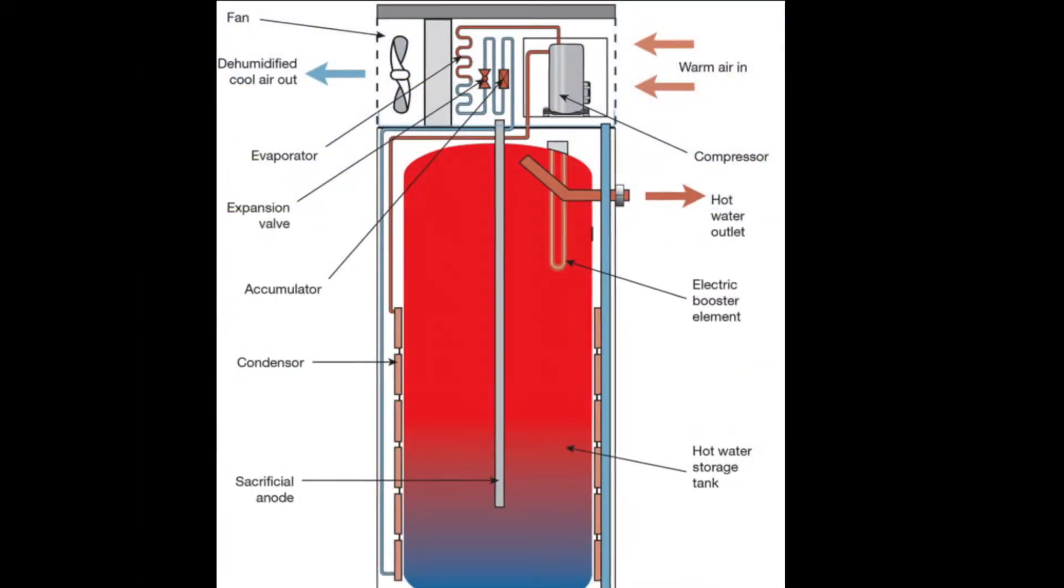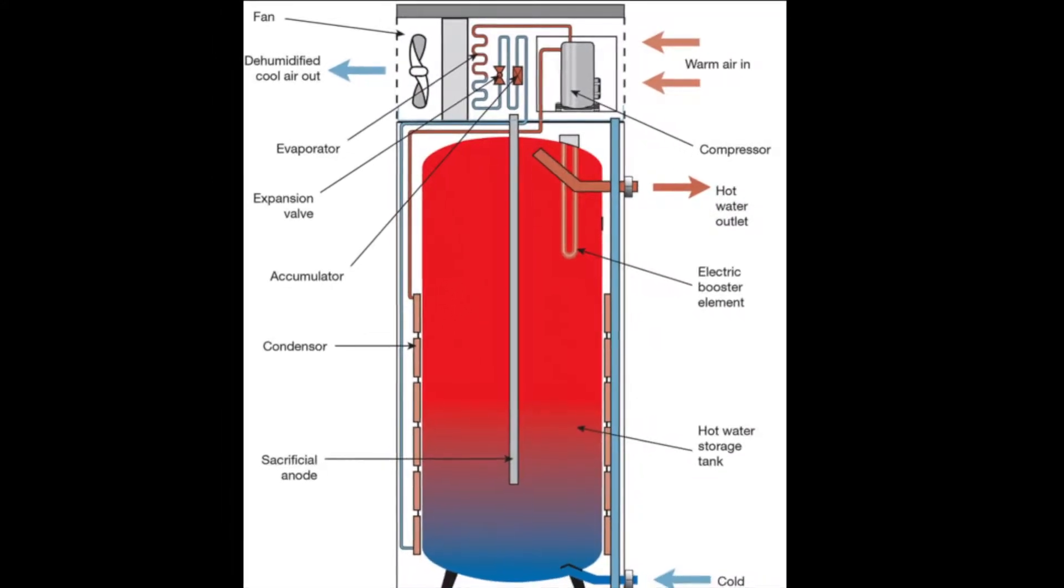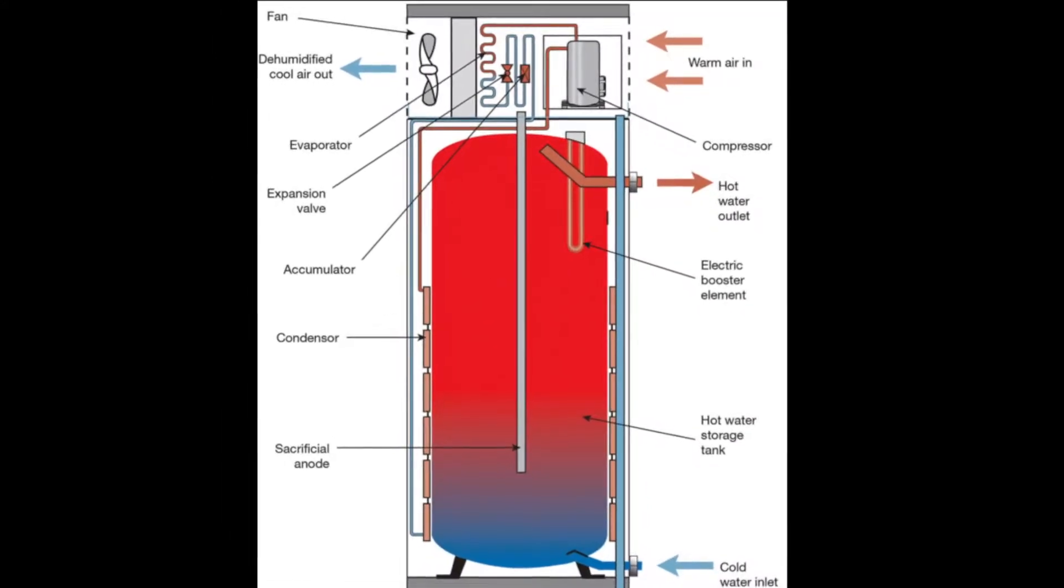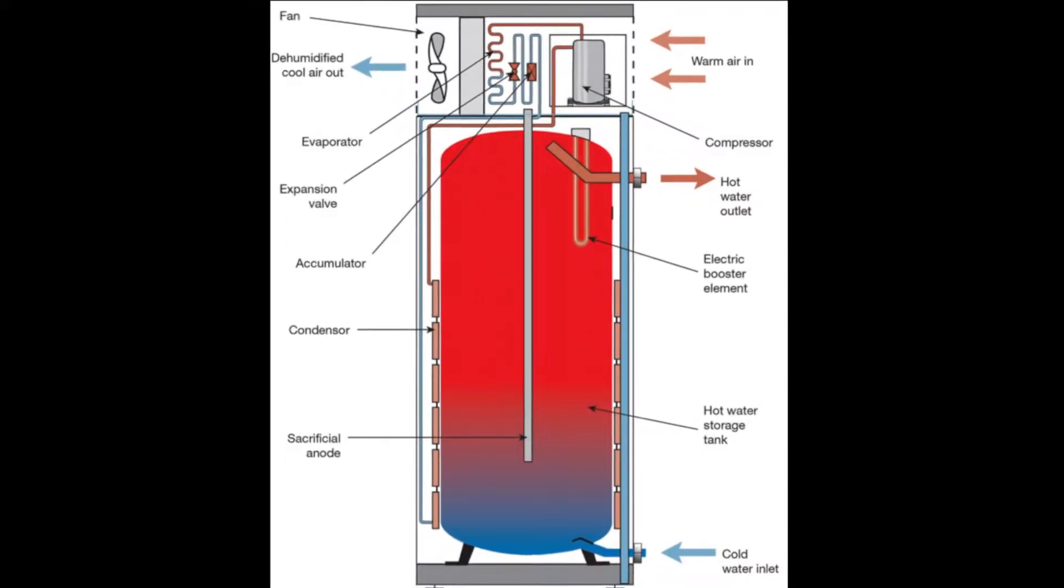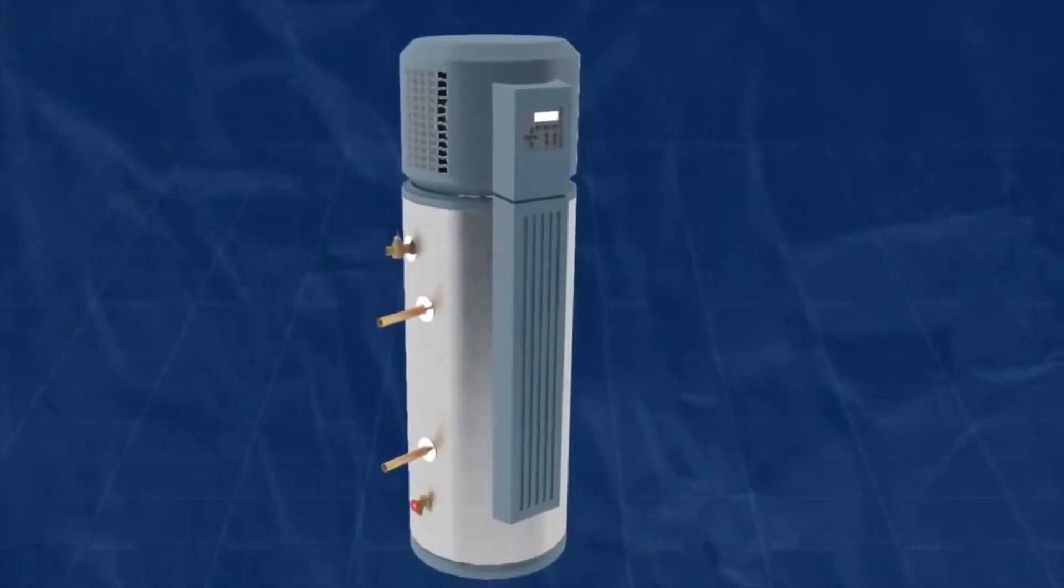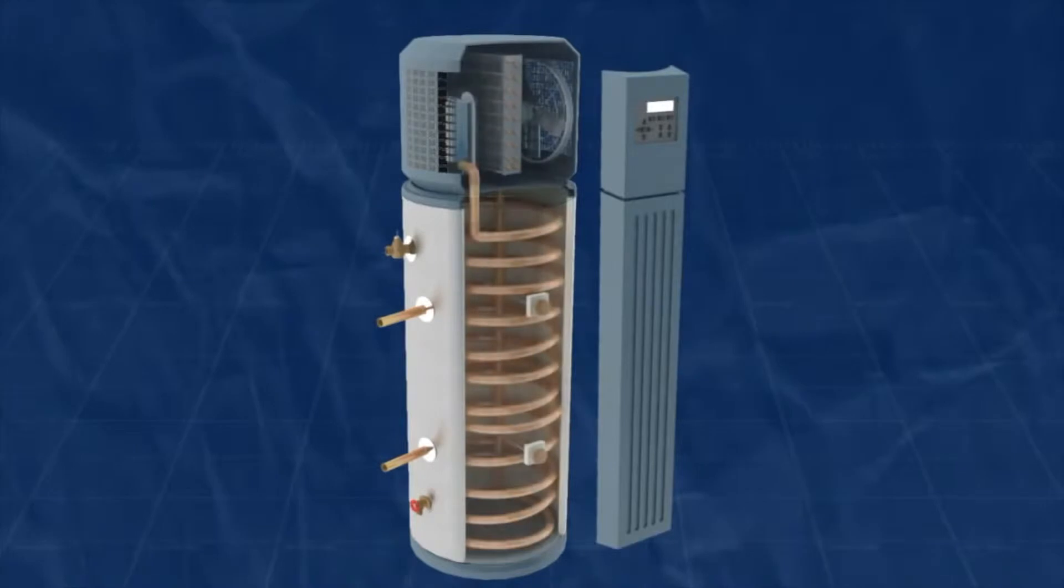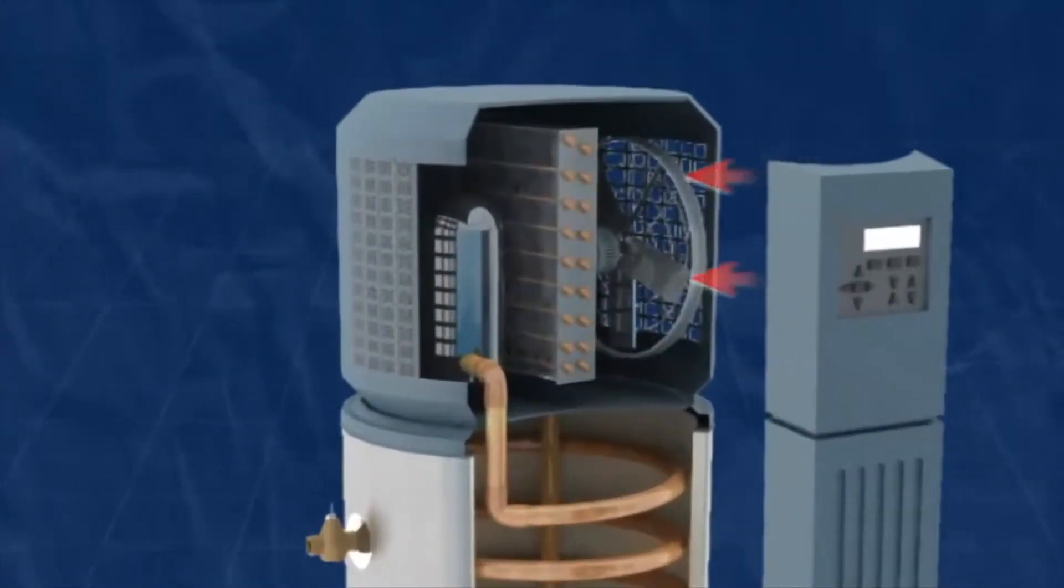Heat pump water heaters work by moving heat from air in the room to water in the tank. To move heat, heat pumps work like a refrigerator in reverse. While the refrigerator pulls heat from inside the refrigerator itself and sends it out into the surrounding room, a heat pump water heater pulls heat from the surrounding air and sends it, at a higher temperature, into a tank to heat water.